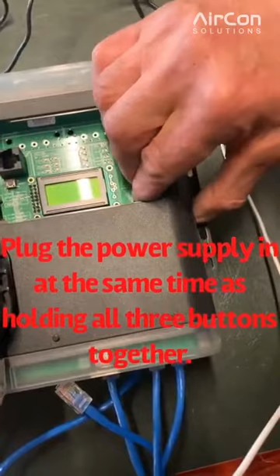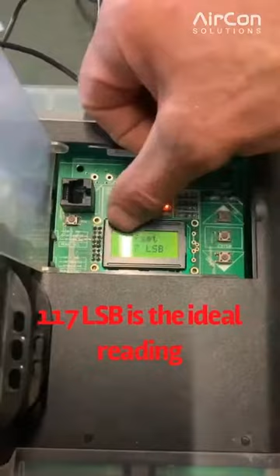Then it says clear, then sensor not cal, and then it's resetting the sensor. An offset of 117 LSB is what we're trying to achieve. That's just resetting the calibration of the pressure sensor module, or transducer, inside the PSDS.